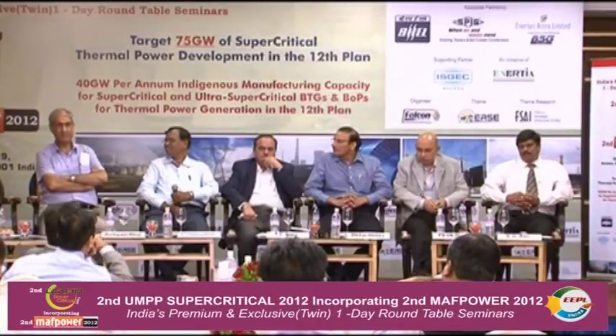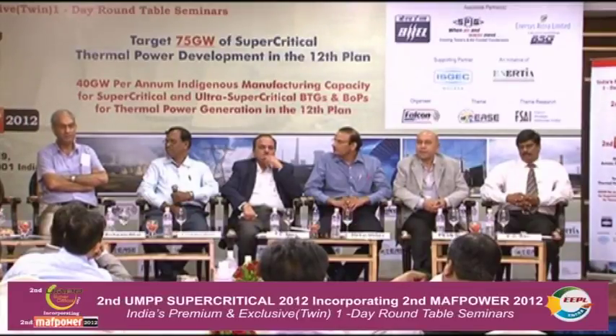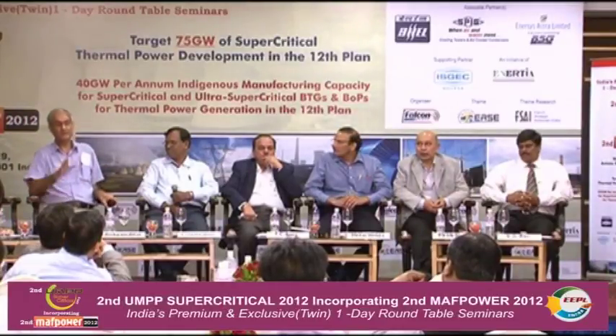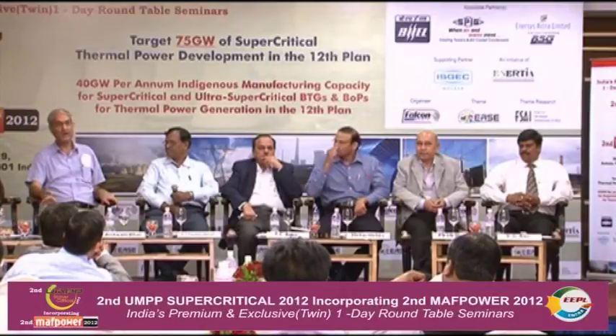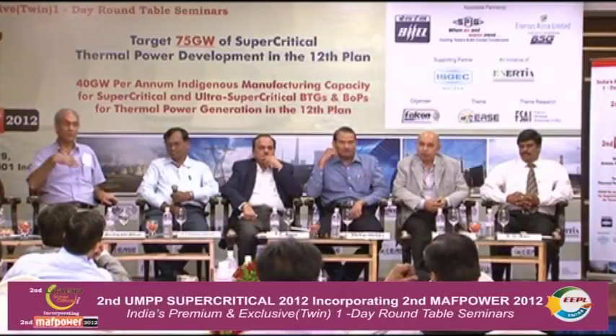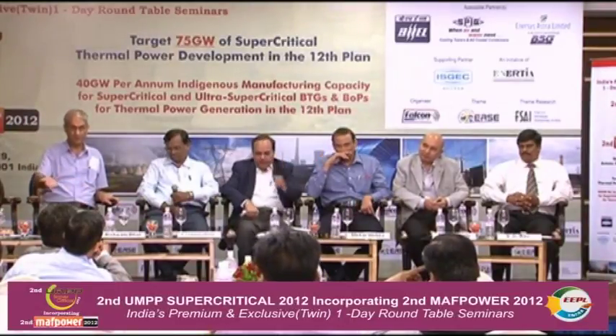R&M could be a major factor, because unlike hydro, where we are not adding capacity but have renovated plants to better capacity, the thermal sector is fizzling away. Huge amounts of money are paid to those plants. We want to keep the tariff down, gain on efficiency by retrofitting, and have an operator, so instead of building new capacity, this could be cheaper in the long run. The margins of the mainline manufacturer are much higher in fresh equipment supply than in retrofit. Very honestly, I'm telling you again that with domestic experience, R&M has not been a success in the country, because capacity has come down after R&M in so many projects.